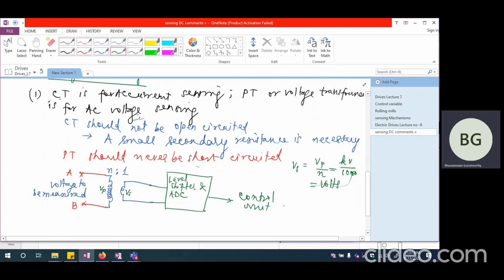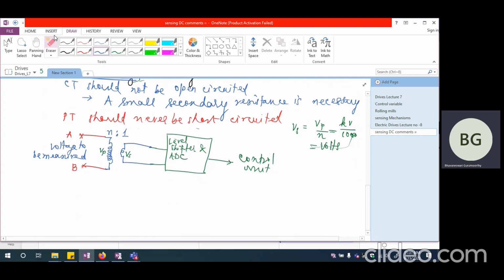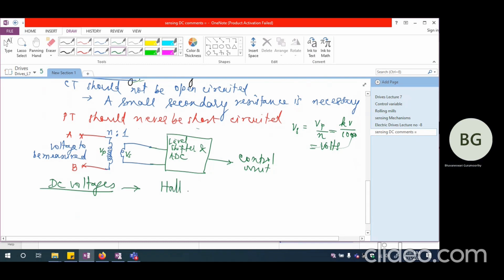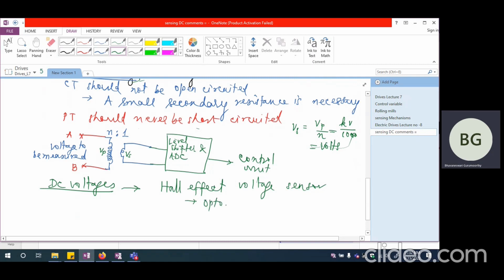So we are going to see that a potential transformer can be used for measuring AC voltages, but I cannot use the potential transformer for measuring DC voltages. DC voltages have to be measured using a Hall effect voltage sensor. The Hall effect voltage sensor should be connected to an optocoupler, and it should be connected to an amplifier, and then it should be fed to the ADC. So this is the way the voltage sensing will also work.